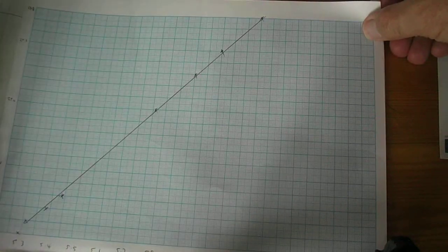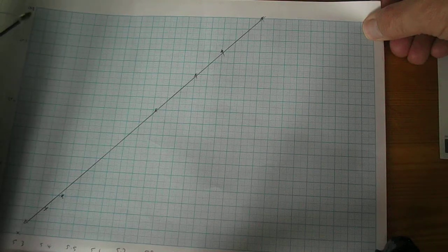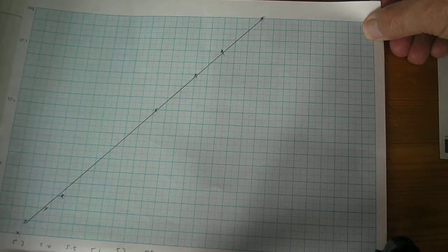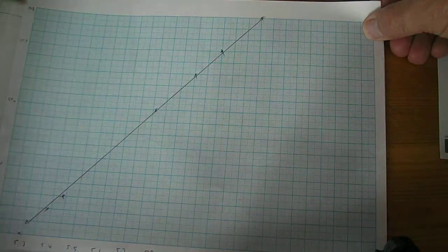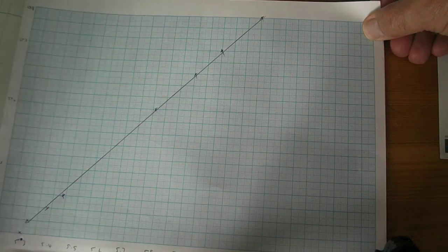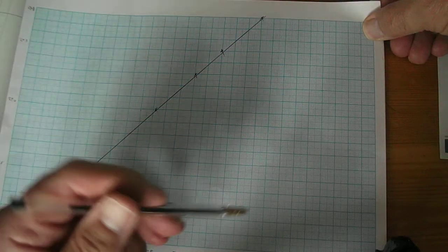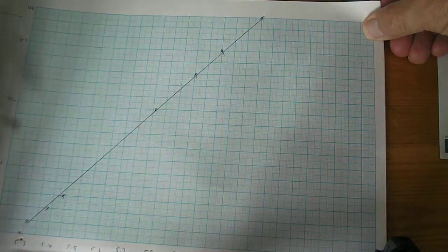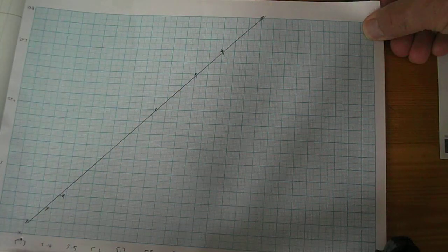And here we can see a graph. I've just done a rough graph here, 230 volts up to 248 because I couldn't quite get 250 on there. But you can see there that the power increases as the voltage increases. It goes from 230 volts, about 5.3 kilowatts, and it goes up to about 6.15 kilowatts. It's probably nearer 6.2 kilowatts actually, just off the graph there.